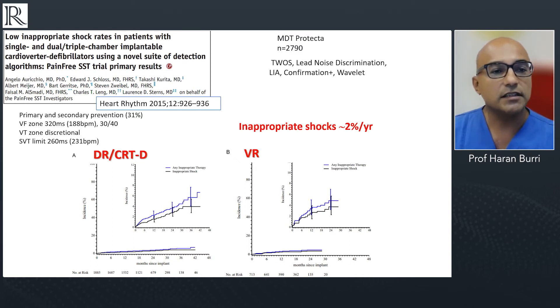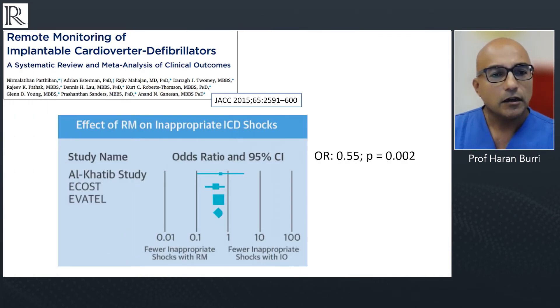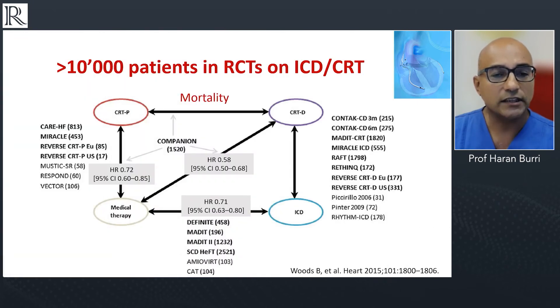There's a very nice study by our chair today, Angelo Auricchio, showing that the rate of inappropriate shocks with transvenous ICDs is now, with the current suite of detection algorithms, only about two percent per year. That's the sort of benchmark we should be expecting from ICD therapy today. We also know that remote monitoring can further reduce the risk of inappropriate shocks by diagnosing lead failure earlier and detecting rapidly conducted AF before a shock is delivered.